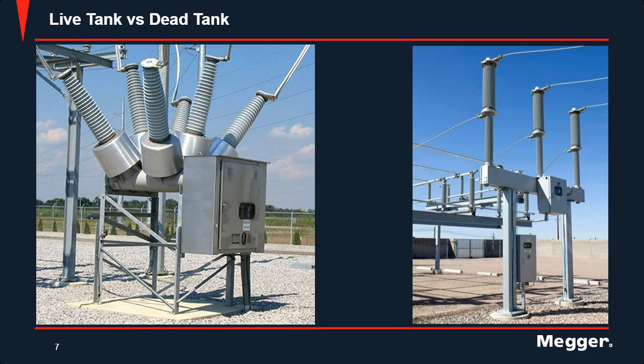So to start off this conversation, we're going to talk about the differences between a live tank and dead tank circuit breaker. For simplicity's sake, a dead tank is a tank that is grounded in service and has more insulating medium in it, such as oil, air, or gas. The CT is mounted on the bushings itself, and it's most common in the US. And with a live tank, the tank is live on the line voltage. It has less insulating medium, oil or gas, and it requires standalone CTs per tower. These are primarily used in European markets. However, they are growing slowly in the US market.